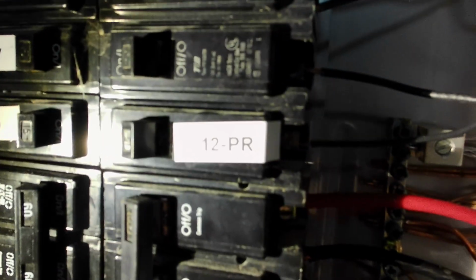The other thing I had to do was put an adapter on my grounding block, because this silver wire is also the ground connection for that sub panel. While I was in here, I went ahead and put all my wires behind my feeder cables like they should be, and I checked the torque on all of these.